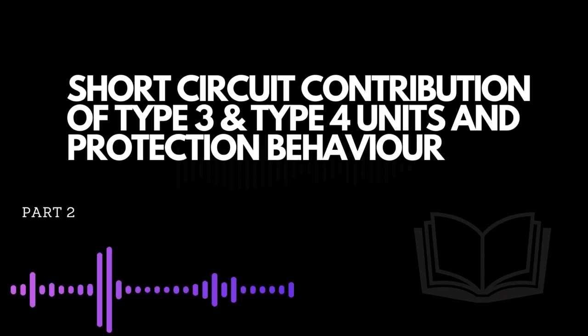The grid codes specify the requirements for PEIG in case of voltage dips, establishing the time that a PEIG has to be connected to the grid and the reactive power supply according to the severity of the voltage dip, in order to improve voltage stability.